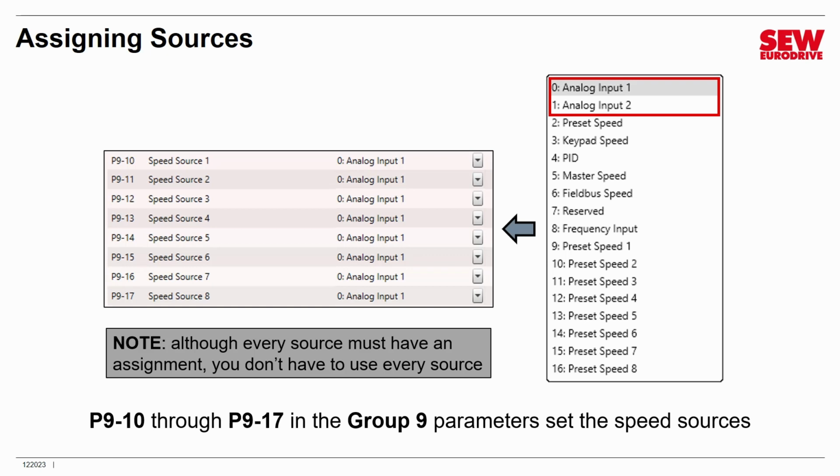These are the two inputs on the VFD. They're typically connected to potentiometers. They could be connected to some kind of variable voltage from another source, but these are usually used for speed control, so you can pick one or both of them if you wish to even have, say, two potentiometers. It's up to you. Then there's the keypad. That's the up-down buttons on the front of the VFD, so you can actually sort of blend keypad control mode with terminal control mode by using this option.